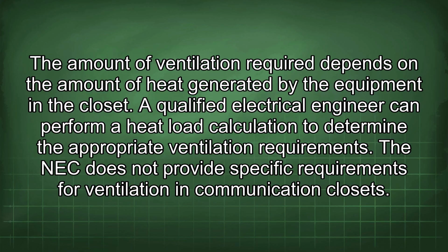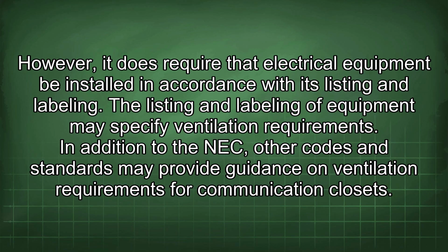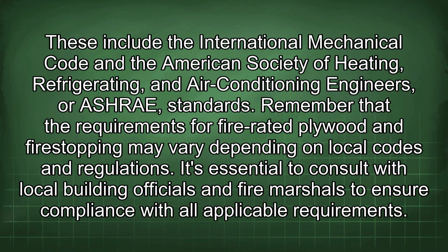The NEC does not provide specific requirements for ventilation in communication closets. However, it does require that electrical equipment be installed in accordance with its listing and labeling. The listing and labeling of equipment may specify ventilation requirements. In addition to the NEC, other codes and standards may provide guidance on ventilation requirements for communication closets. These include the International Mechanical Code and the American Society of Heating, Refrigerating, and Air Conditioning Engineers, or ASHRAE, standards.